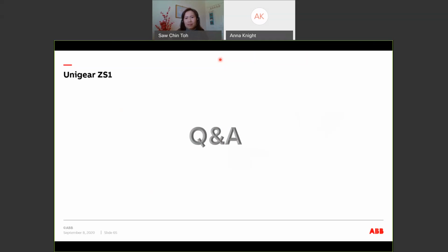Okay, thank you. The next question is: have you internal arc tested the switchgear with the LV door open? This is a very common question raised by customers. The switchboard has been internal arc tested based on IEC standards. In the IEC standards, it actually calls for all the doors to be closed as one of the criteria. But of course we understand a lot of the requirements nowadays, because customers may need to access the low voltage compartment while the switchboard is live, and they have concerns about safety while work is done on the LV compartment. So we also carried out tests on the UniGear ZS1 cubicle with the LV door removed, and we passed the test as well.